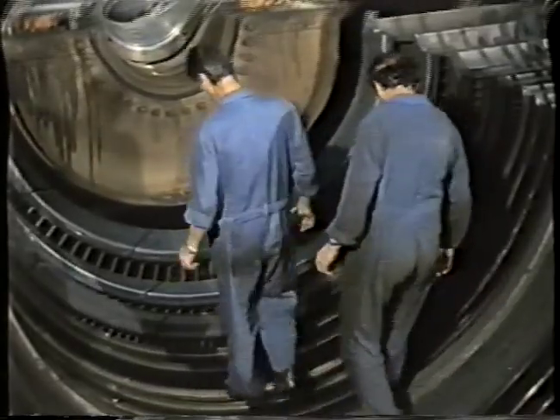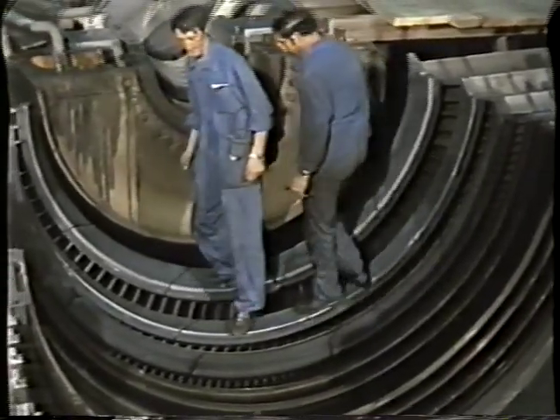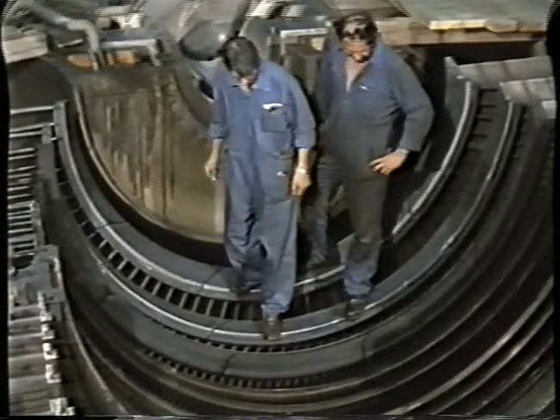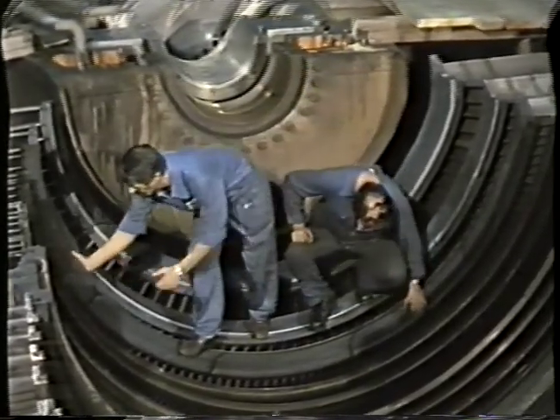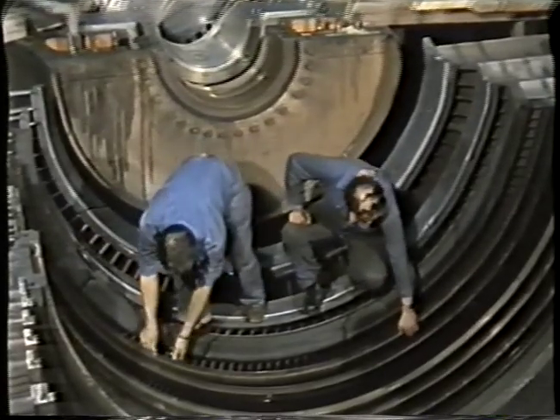A visual inspection of the shape and form of the stator parts is followed by detailed inspection of all the blades, in order to detect any possible cracks in them, replace them, and repair other small defects.